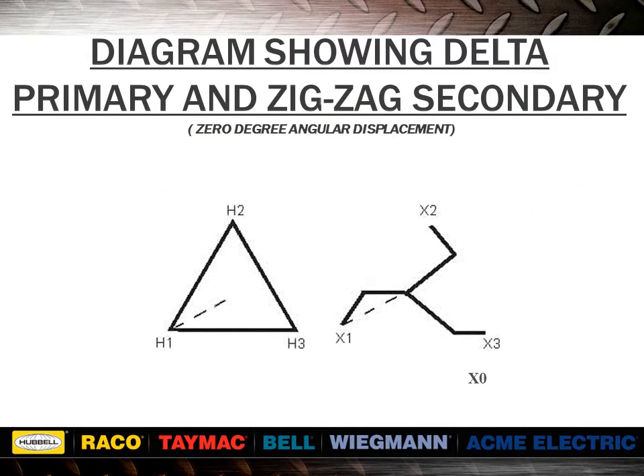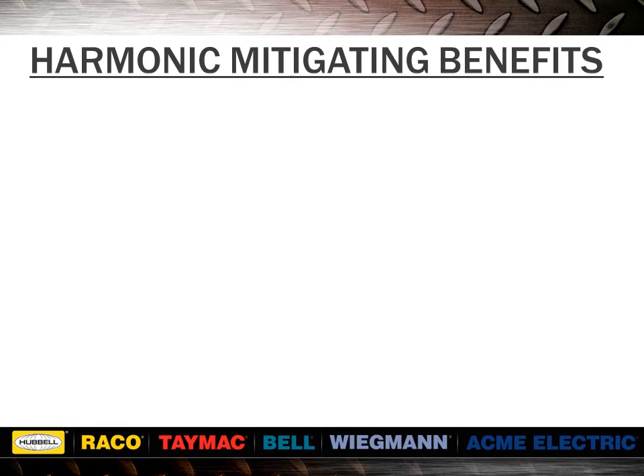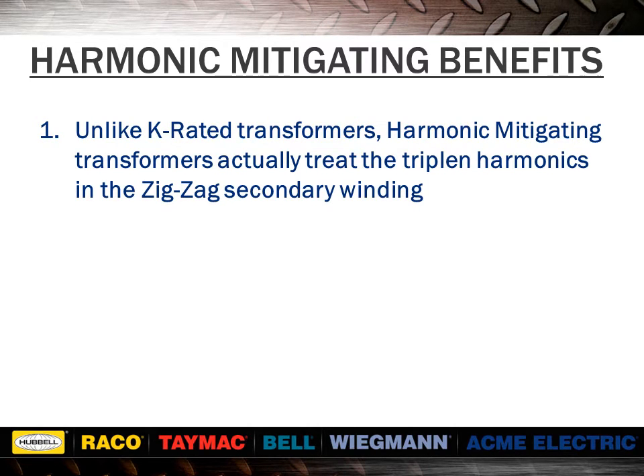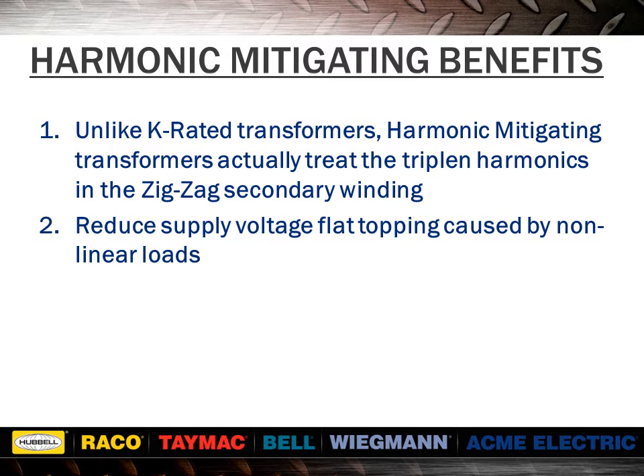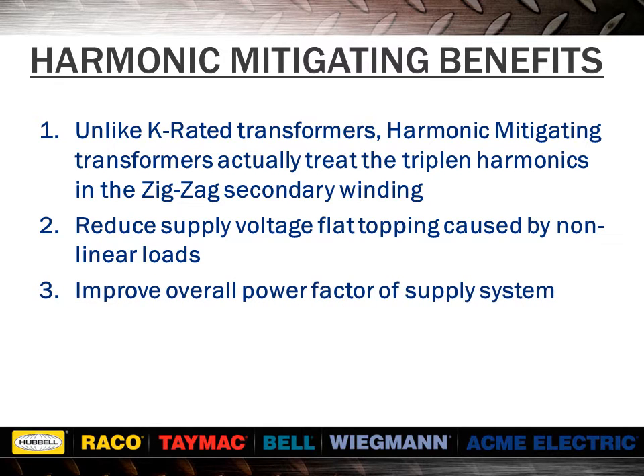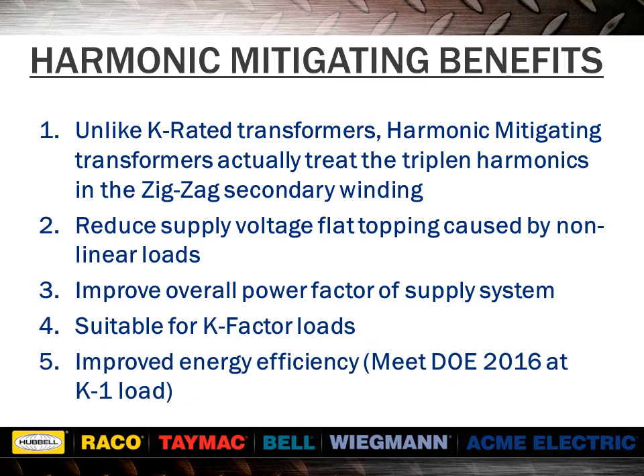Here we see a diagram that shows the delta primary and the zigzag secondary. There are several benefits to harmonic mitigating transformers. Unlike k-rated transformers, harmonic mitigating transformers actually treat the triplen harmonics in the zigzag secondary winding. They reduce supply voltage flat-topping caused by non-linear loads, improve overall power factor of supply systems, are suitable for k-factor loads, and provide improved energy efficiency which meets the DOE 2016 at k-1 load.